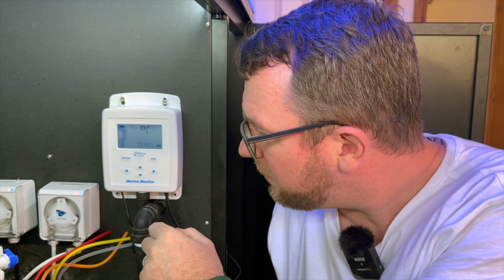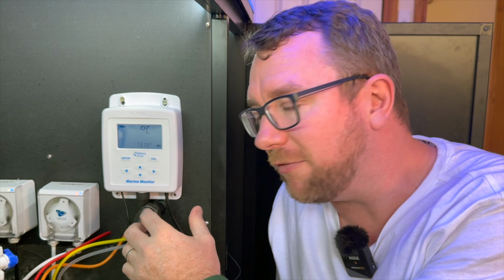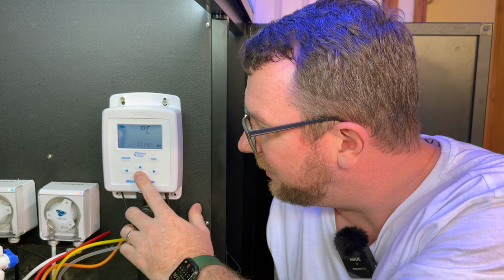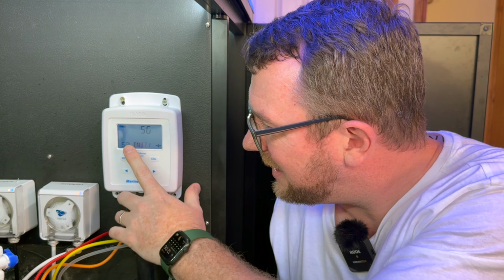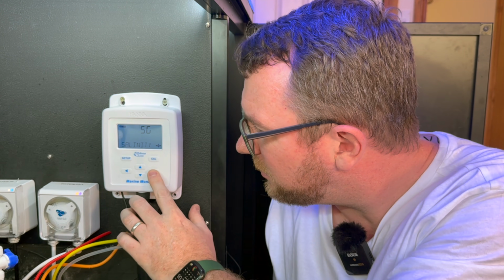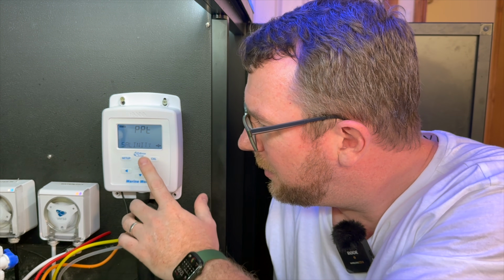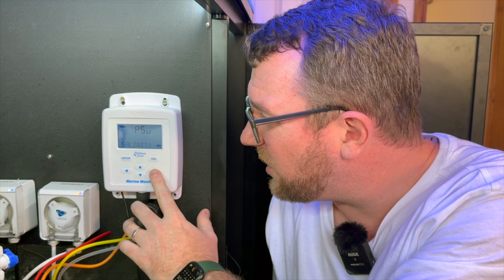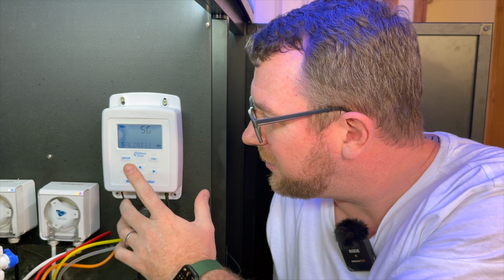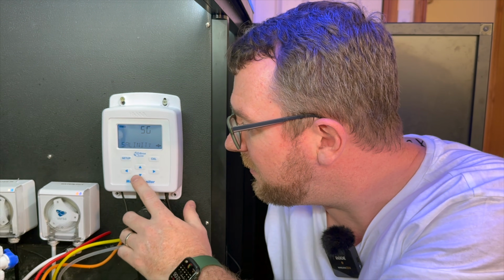And first of all, we've got temperature. We can measure that in Celsius or Fahrenheit. I'm happy with Celsius, so we'll leave that. Press down for the next one. Salinity is specific gravity. We can scroll through and change that to parts per 1,000. We can change that to PSU or specific gravity. I'm going to leave it at specific gravity.